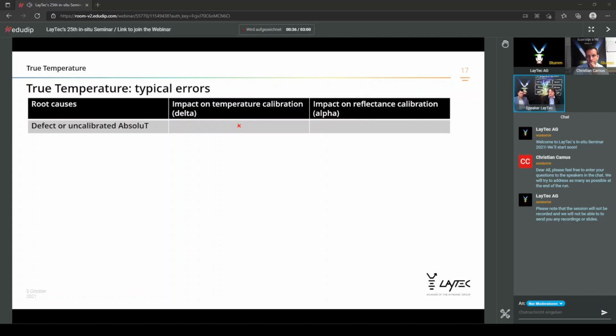So to start with, the very common effect we can see is that the AbsoluT is either not calibrated anymore, or in some rare cases was even defective, meaning that the emission was no longer calibrated, no longer consistent with its reference values to reflect the corresponding intensity for the temperature it is calibrated to, for 950 nanometers emission. So this root cause will have a direct impact on temperature calibration, the so-called delta calibration. Delta is the name of the calibration factor the EpiNet calibration sequence will determine out of this calibration.